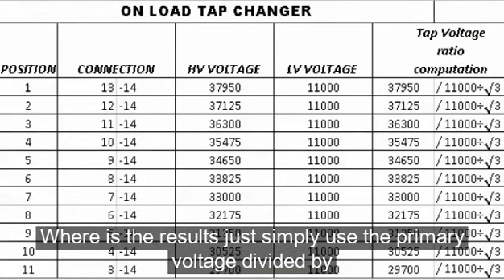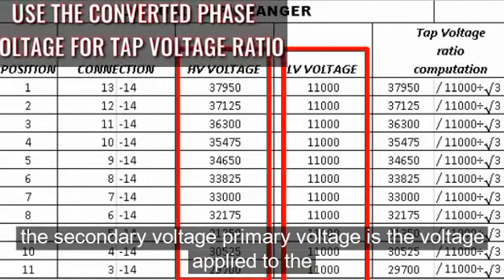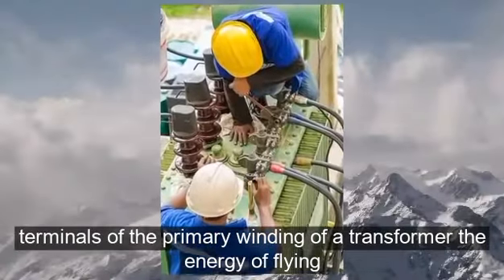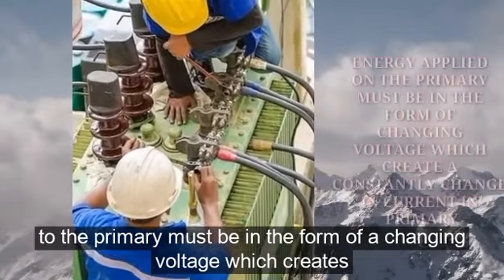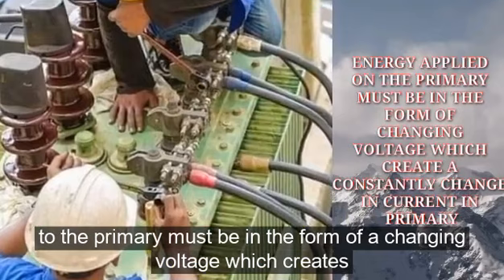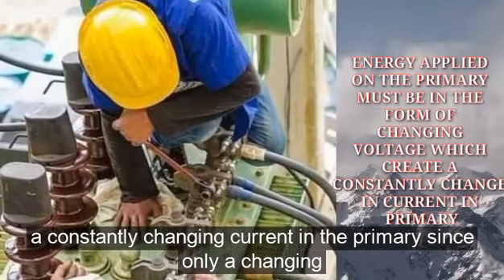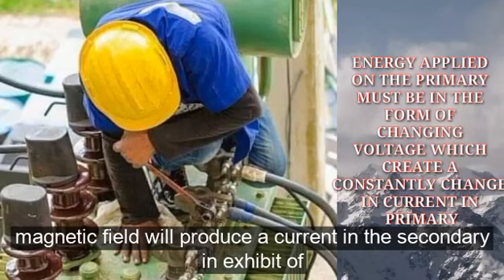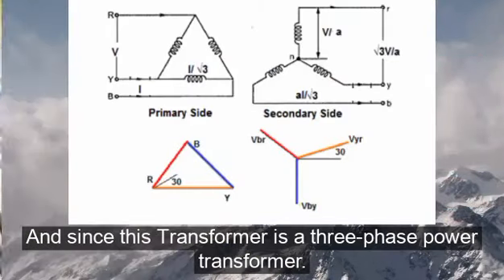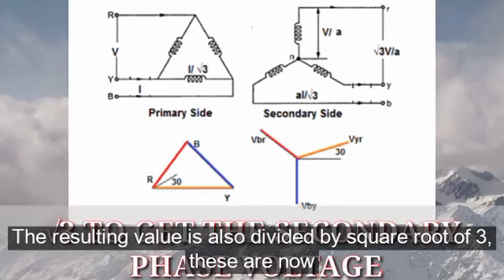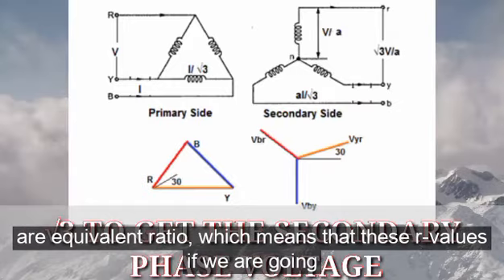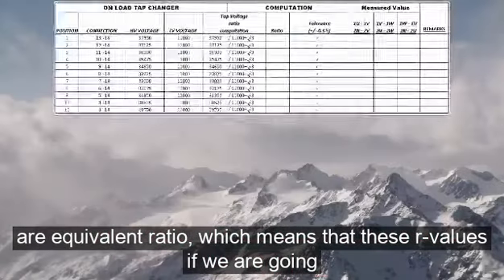It starts by finding the equivalent tap voltage rated ratio, where as a result, you simply use the primary voltage divided by the secondary voltage. Primary voltage is the voltage applied to the terminals of the primary winding of a transformer. The energy applied to the primary must be in the form of a changing voltage which creates a constantly changing current in the primary, since only a changing magnetic field will produce a current in the secondary and exhibit a secondary voltage. And since this is a three-phase power transformer, the resulting value is also divided by the square root of 3. These are now our equivalent rated tap ratio, which means that these are values that we are going to use as reference for our tolerance.